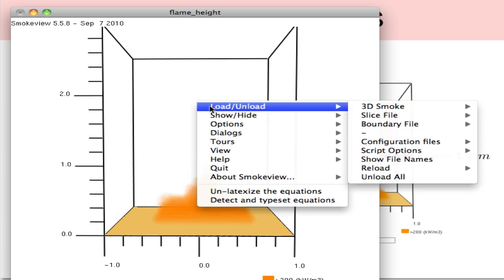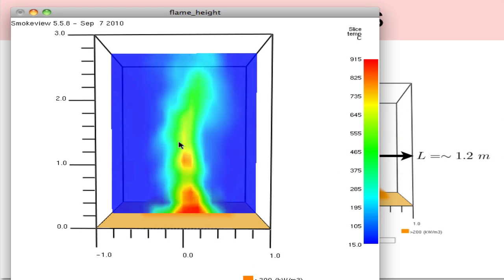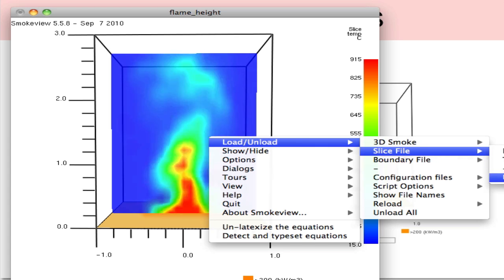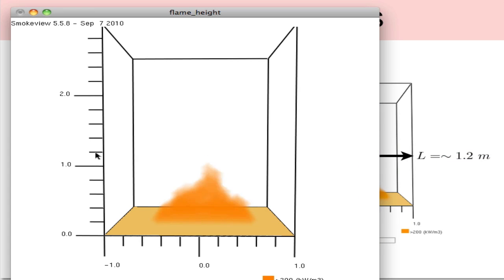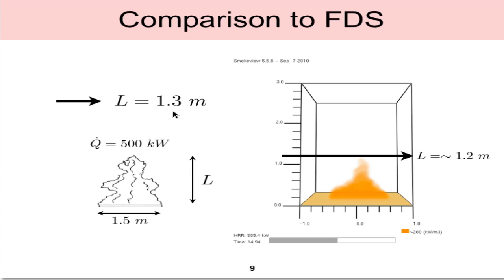Above here, if I turn on a slice file of the temperatures, we can see hot gases exist above the physical flame height, on the order of 400 to 500 degrees Celsius. That's defined as the plume region. So from the simulation, we can see that the flame height predicted is about 1 to 1.2 meters.